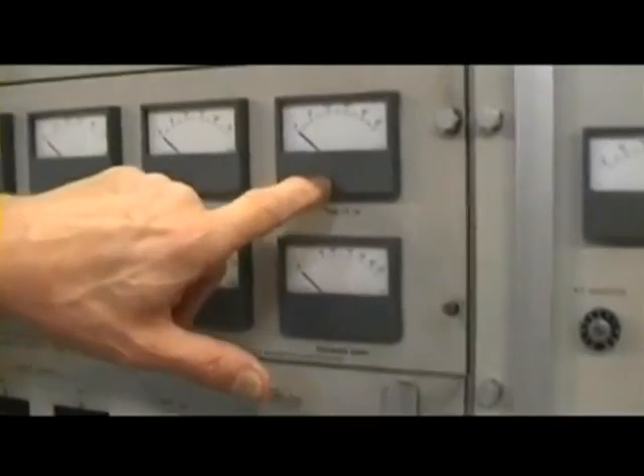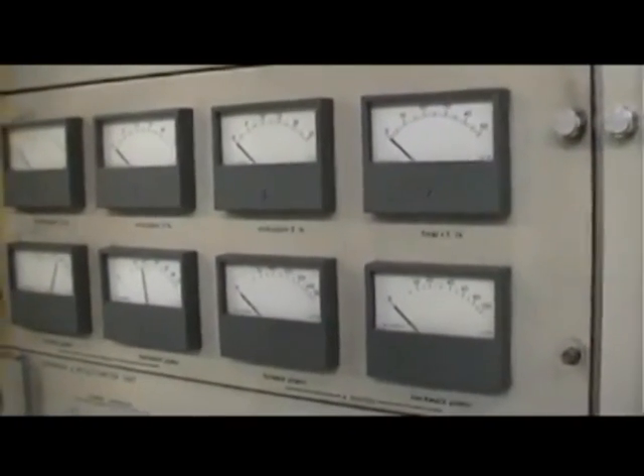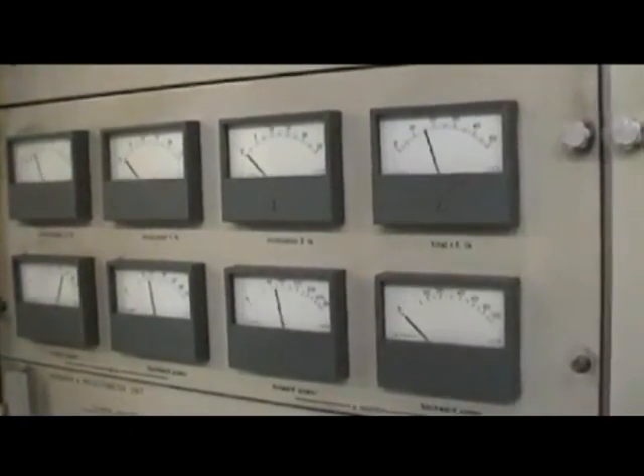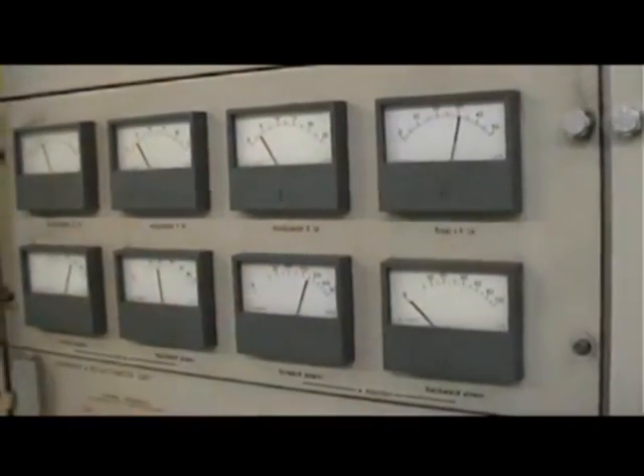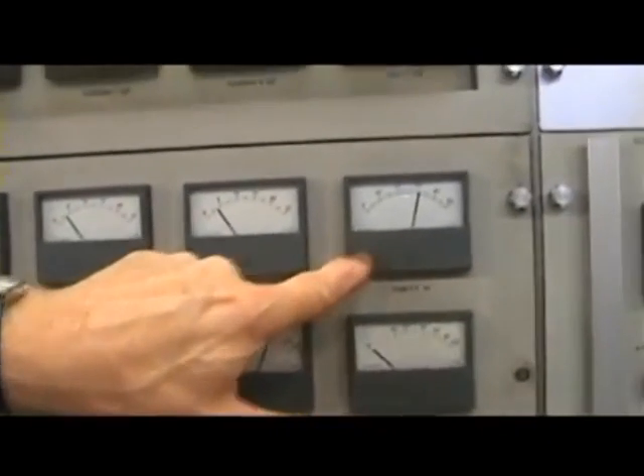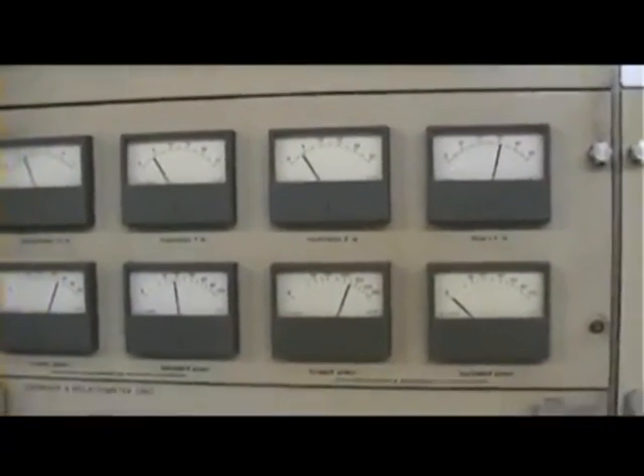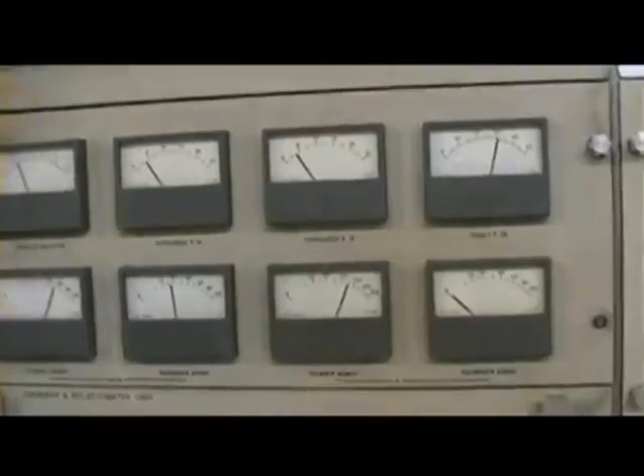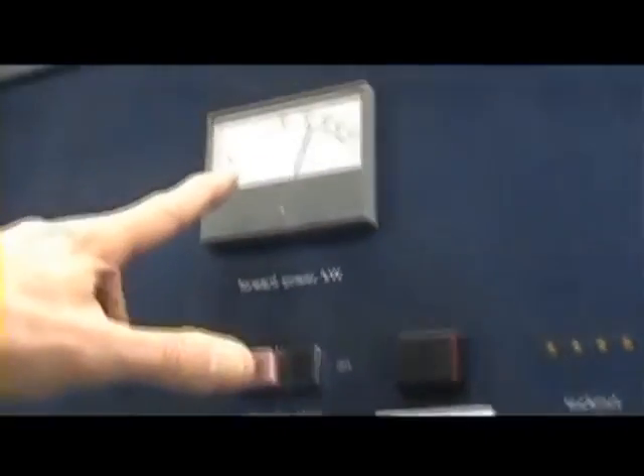On this, you get a low power version, and then it comes up to full power. So if you just look at the cathode current meter, you'll see it will come on at a low value to start with. Right, here we go on the switch. And up we go to 30 amps. 30 amps of cathode current on the final stage at 11 kV, about 300 kilowatts input. If we just look up here, we'll see we've got about 250 on the out.